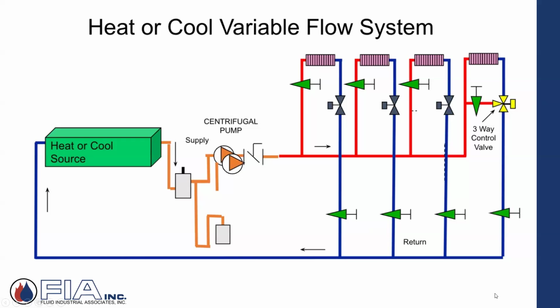So that as the valves close, why would they close? Because the space temperature was satisfied, heating or cooling. And they would do their thing, again, with a constant speed pump at the time, they would have at least this bypass, this three-way valve, to provide an outlet.